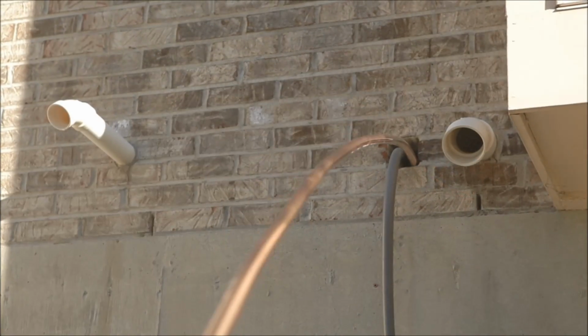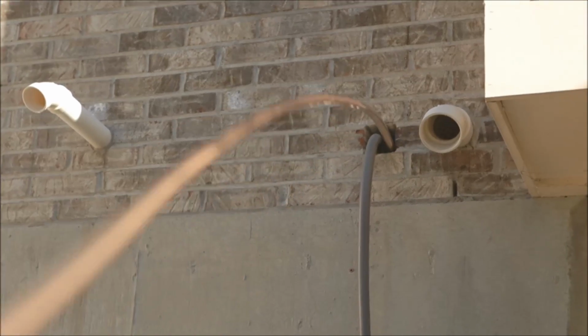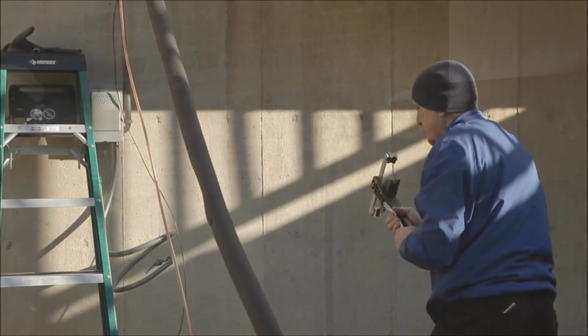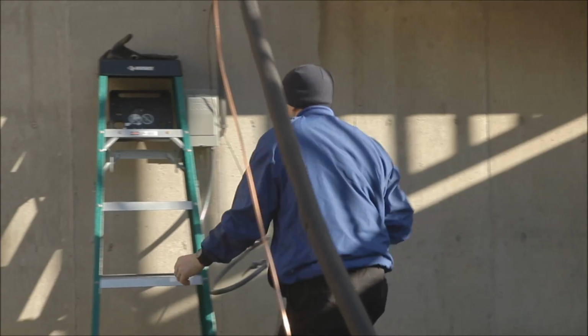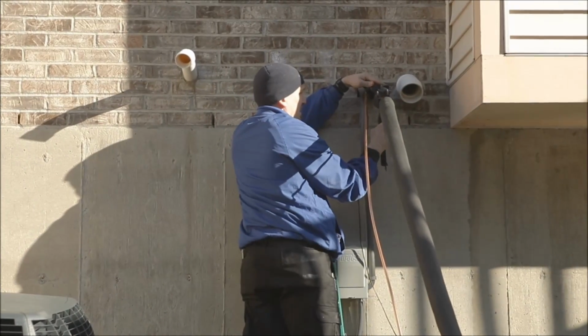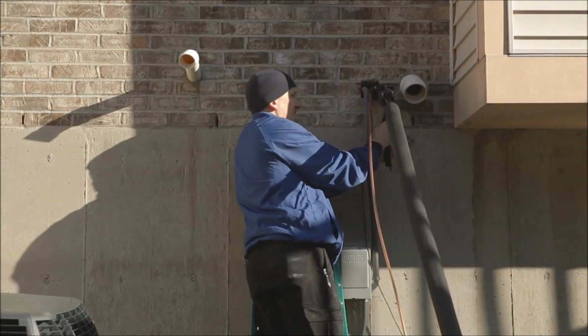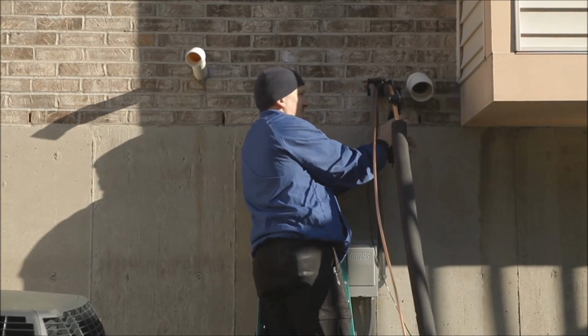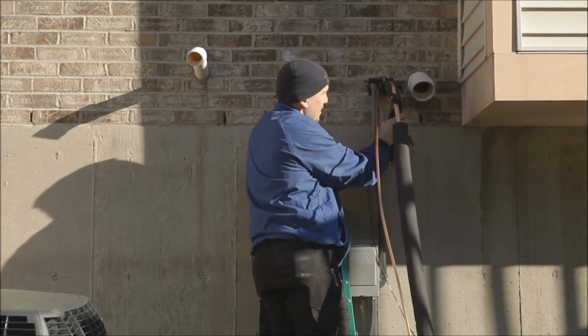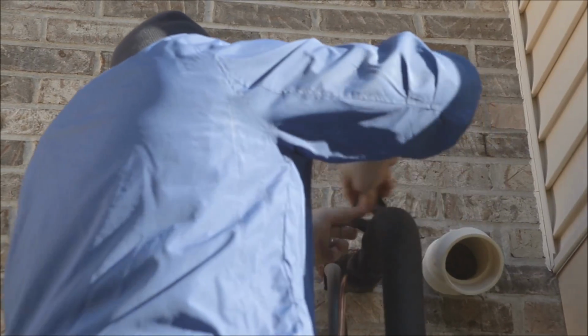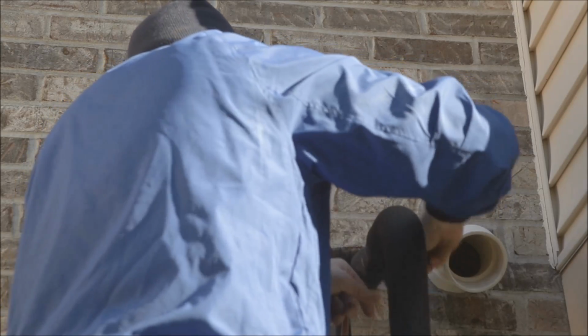The next step for the technician is to install the copper tubing. Using a copper tubing bender tool saves the technician time. This tool reduces the number of connections that require brazing, which also lessens the chance of leaks. Taping the insulation helps prevent excessive condensation and ensures designed capacities, temperatures, and pressures are maintained.